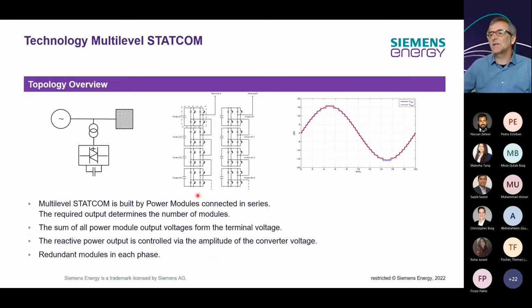There is a redundancy inbuilt. So if one module would fail, it will be bypassed and you will continue operation. You get an alarm, you can replace the module during the next shutdown, but you will not trip the system. So for the availability of the system, that's a very good measure to maximize the availability of the system.